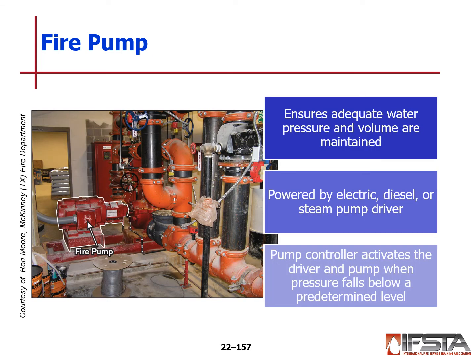Some systems may be equipped with an auxiliary fire pump. This ensures that adequate water pressure and volume will be maintained, especially until we arrive on scene to supplement that supply. This is powered by electric, diesel, or steam pump driver. The pump controller activates the driver and the pump when the pressure falls below a predetermined level. So if a head pops and it begins to flow water, that pressure will then drop. You now have a flowing pressure, and that will activate. Once it drops below a certain level, it will activate the pump.